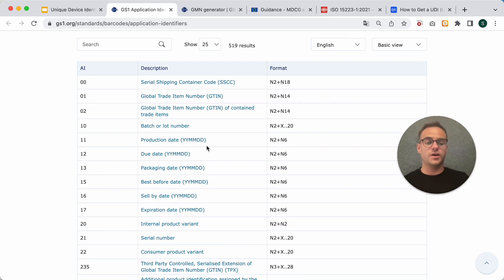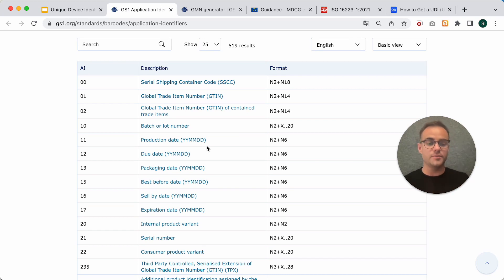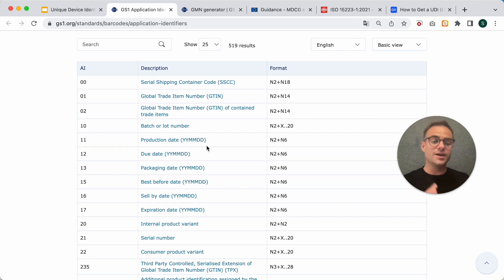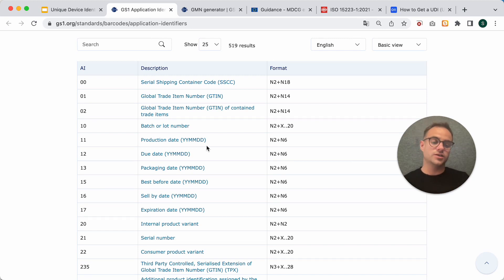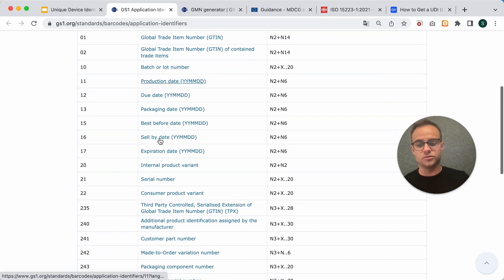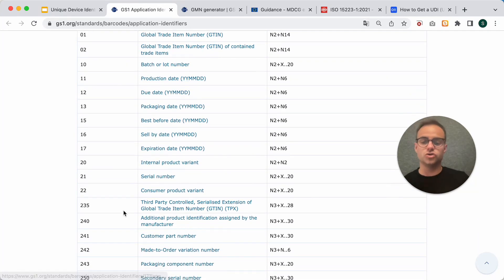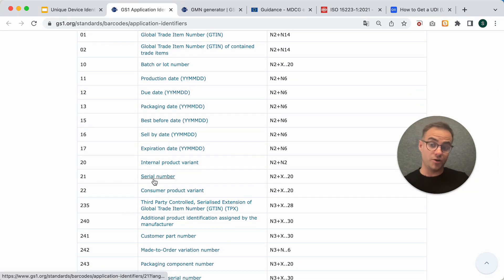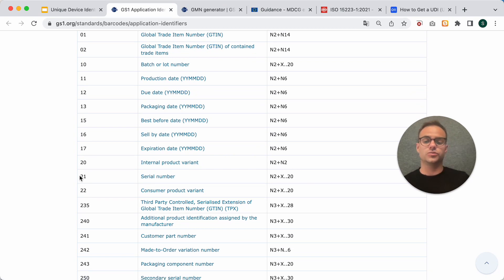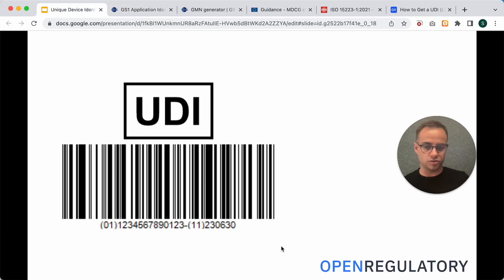But if you have a physical product, something like a pacemaker, then you would need a different UDI-PI for every single piece that you produce. So, it makes more sense to then use something like a serial number as the UDI-PI, which would be encoded with 21. And you would put 21 and the serial number.